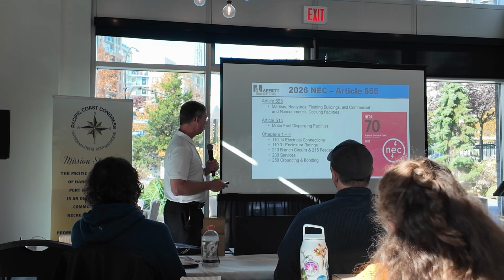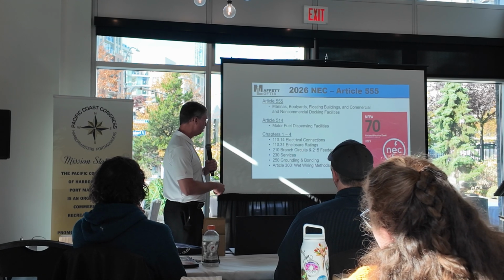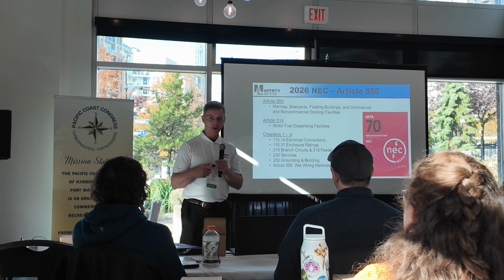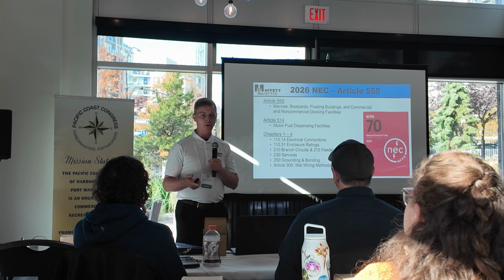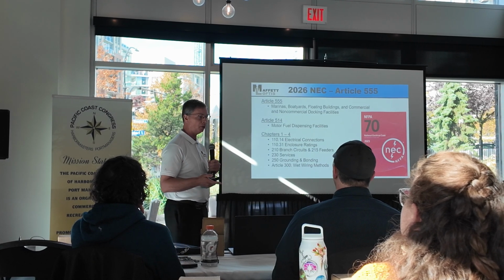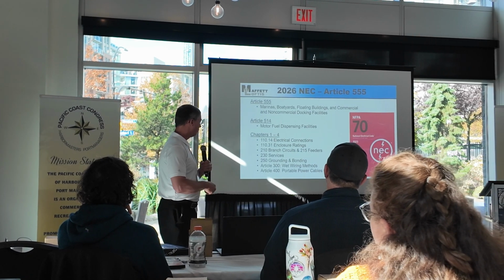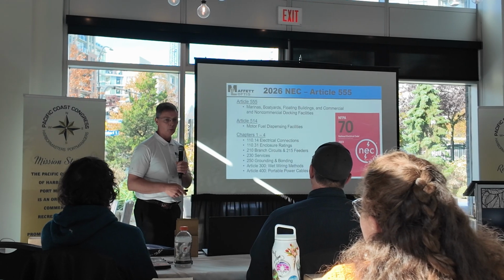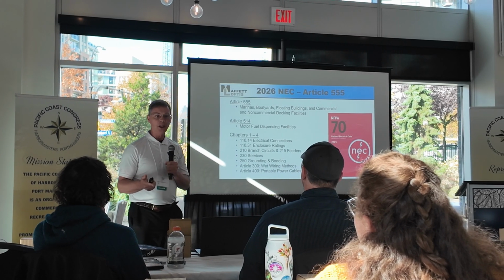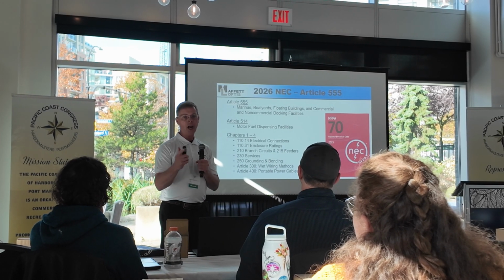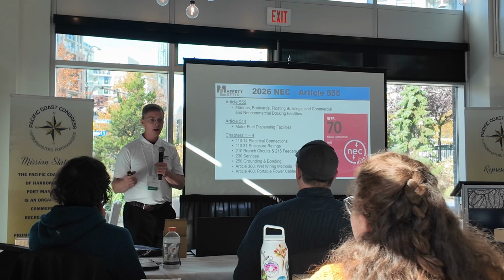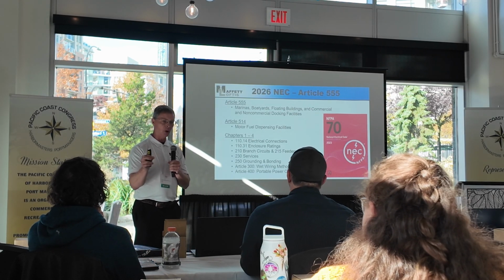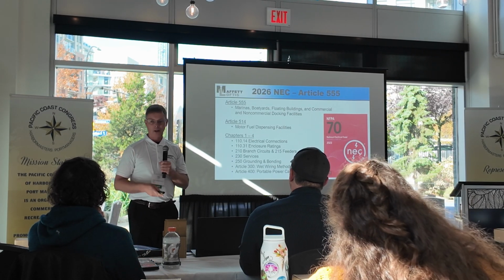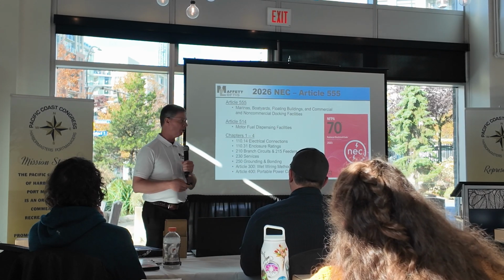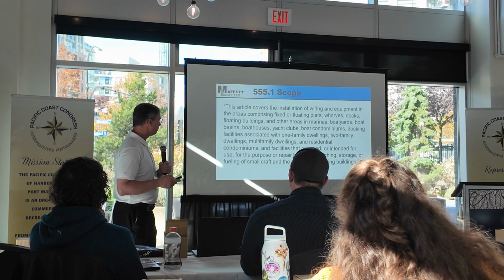So all these chapters 1 through 4, wiring methods, any listed wiring method that has an insulated grounding conductor is approved for marinas. But you look at chapter 300 for that. 400 is portable power cable, which is type G, type W, type G-GC cable. So it's under 400. So all chapters 1 through 4 apply to marinas, but Article 555 can modify those chapters 1 through 4 for specific installations of marinas.